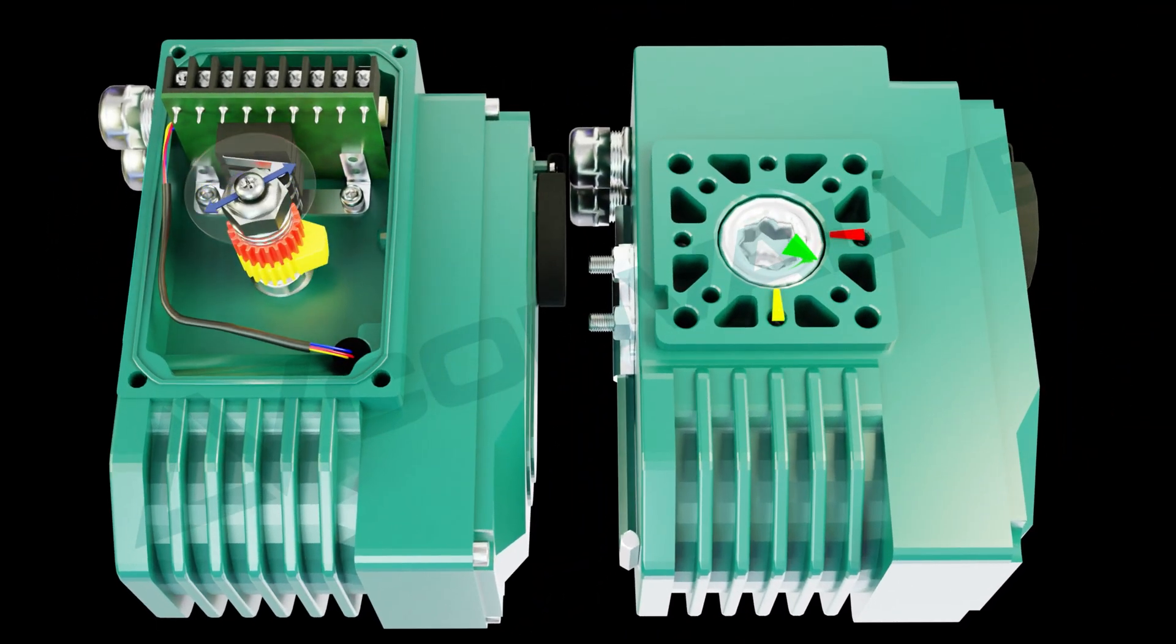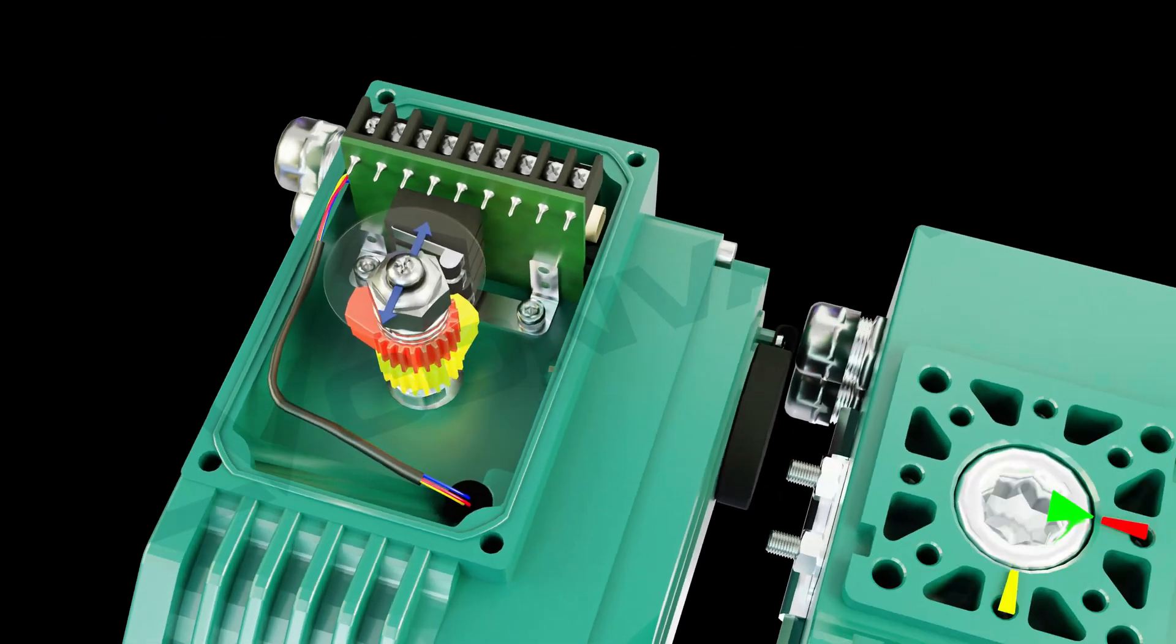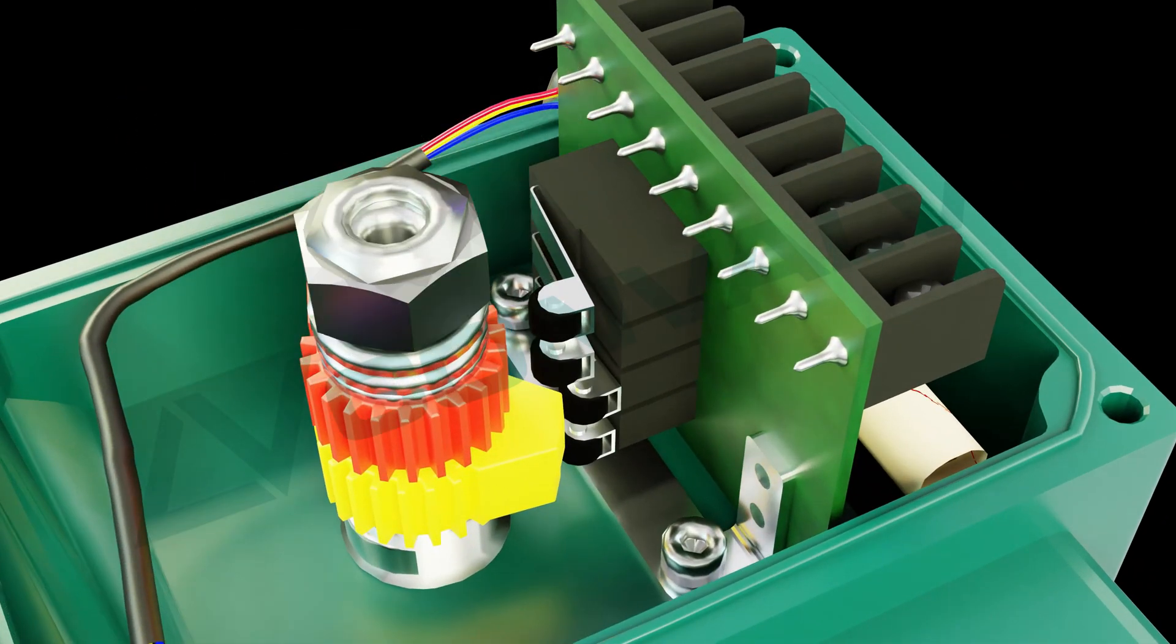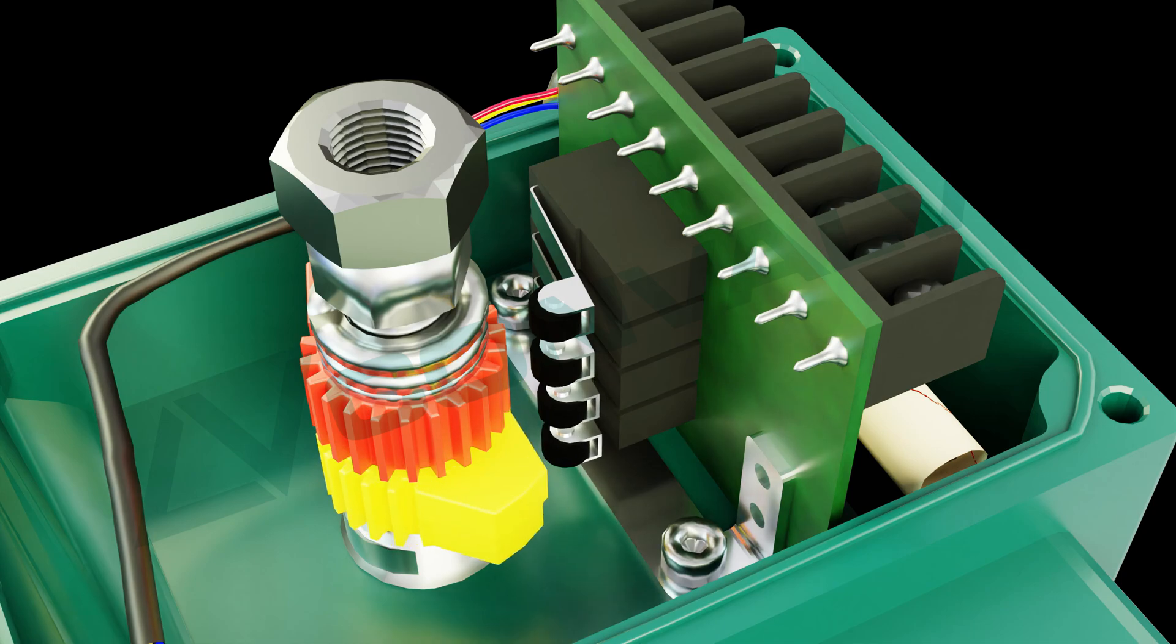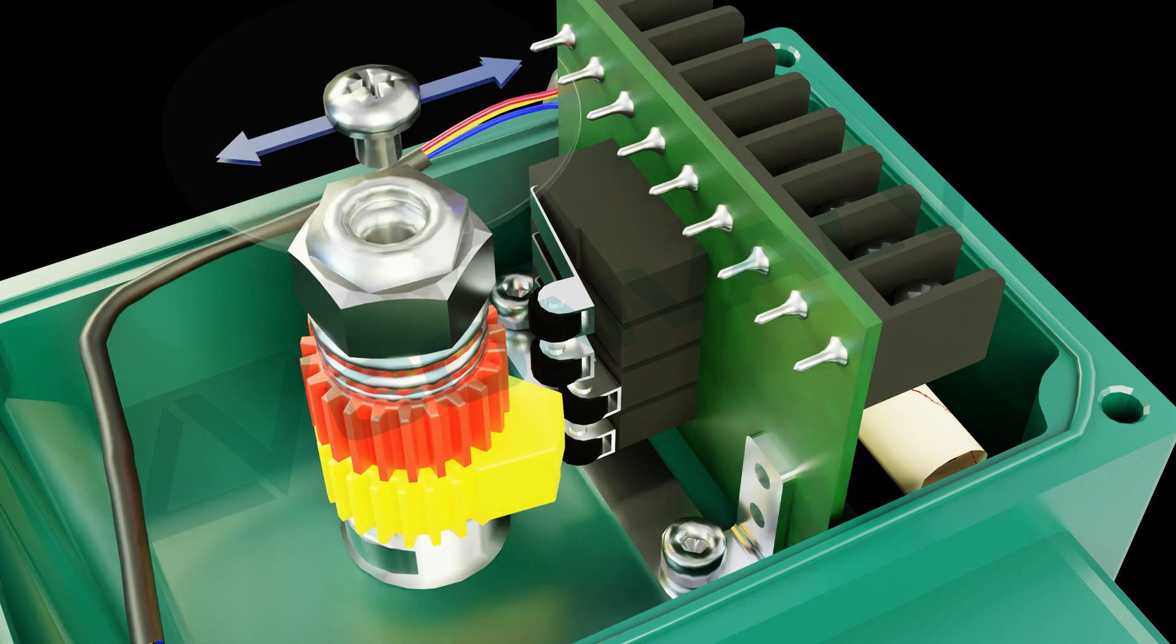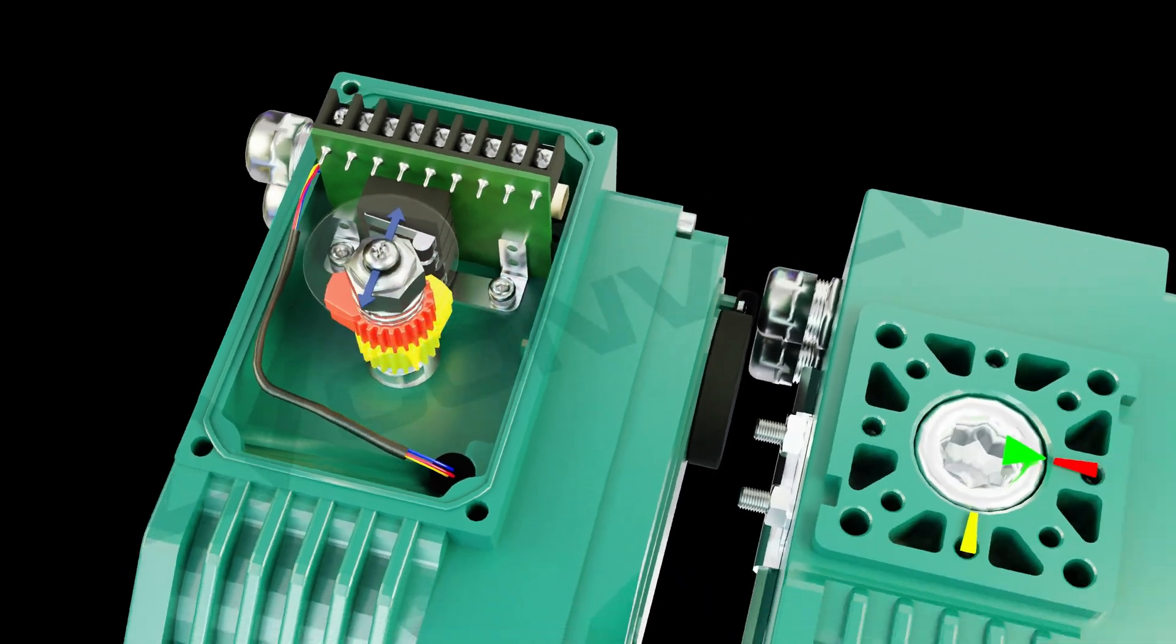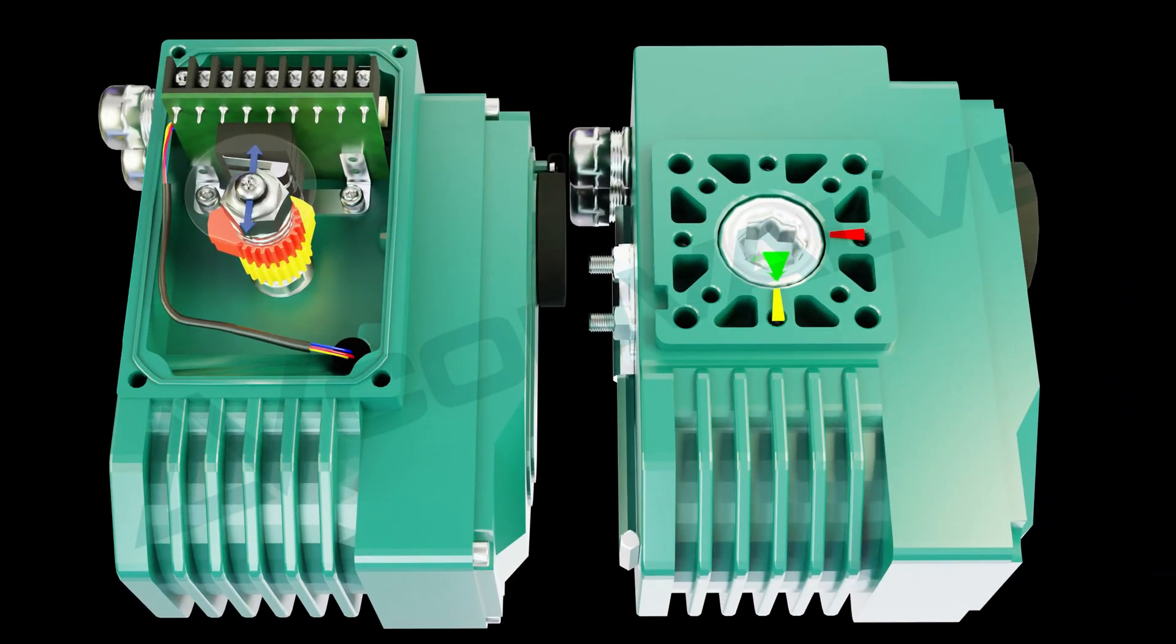Setting the full open position: manually adjust the electric actuator to its fully open position. Use a lever to loosen the nuts on the limit cam, rotate the limit cam until the corresponding open limit switch yellow is activated. Ensure that the actuator's connection to the valve is properly aligned and securely positioned. Once everything is correctly aligned, securely tighten the cam nut.